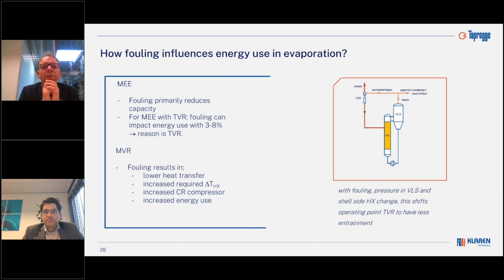Because if you put a black box around an evaporator and you make an energy balance, the stream where you lose your energy is the vapor stream that goes to the condenser for an MEE. And as you can imagine, at the moment that the entrainment, so the amount of vapor that is sucked in by the TVR, goes up, less energy goes to the condenser, so that's good. But what happens with fouling is that the pressures change, and you get less entrainment. Less entrainment means more vapor that goes to the condenser, and more vapor to the condenser means a lower energy efficiency. If you look at the total energy efficiency of the plant, that's around 5 to 10%. But if you calculate the numbers over a year, it has a really substantial benefit in terms of money, but also, of course, in terms of energy and emissions.